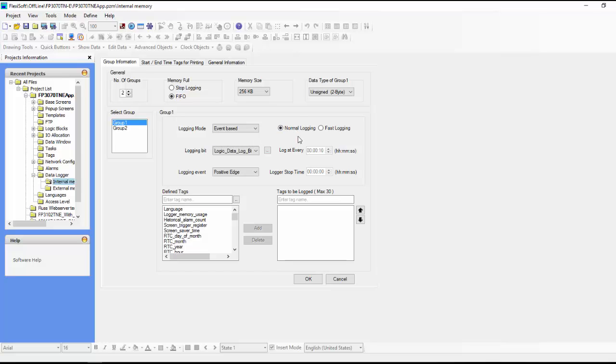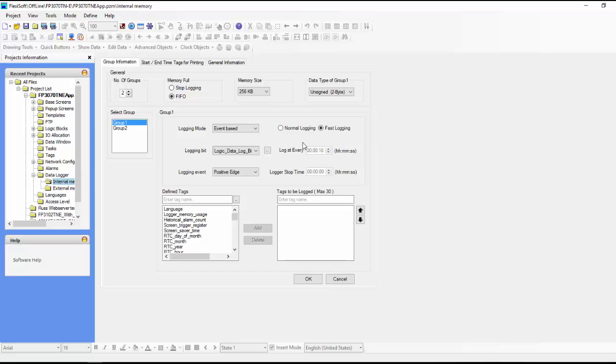So we can do normal logging. And this is just the bit turns on, and I think the bit probably has to be held on for 20 or 30 milliseconds, something like that, to be able to capture it. Or if it's something like a transient signal and you want to create a log on a very short pulse, like one millisecond or five milliseconds, then you'd have to set this to fast logging. So most of the time you just choose normal logging.